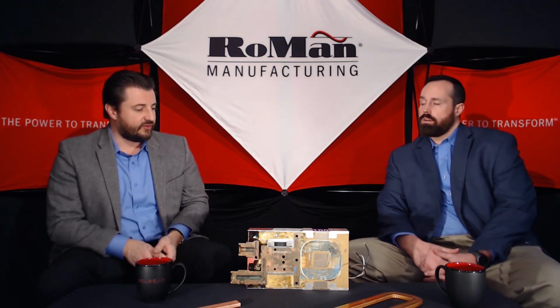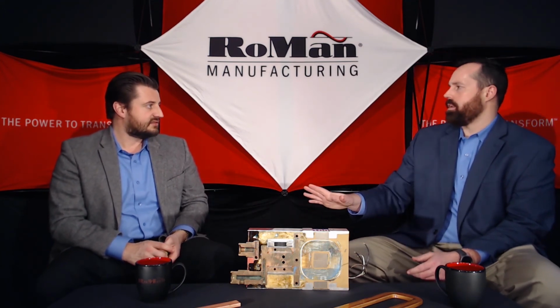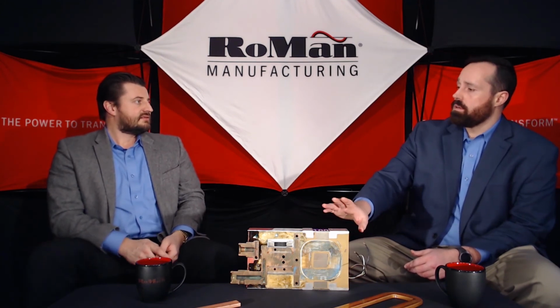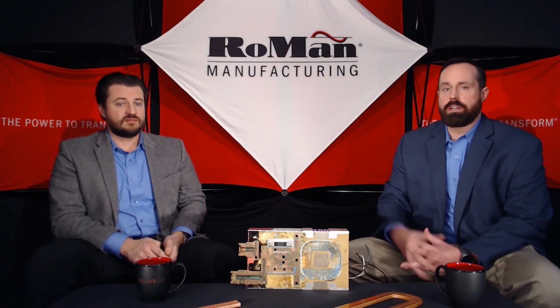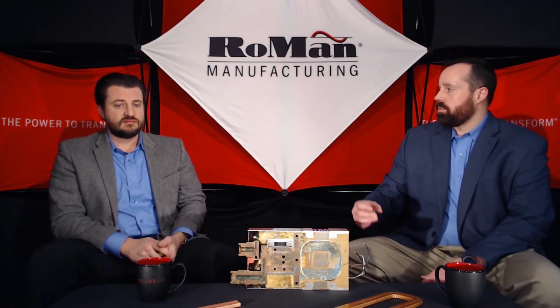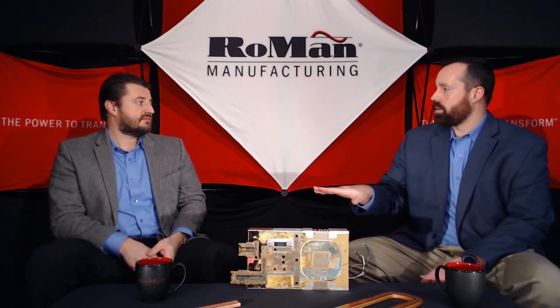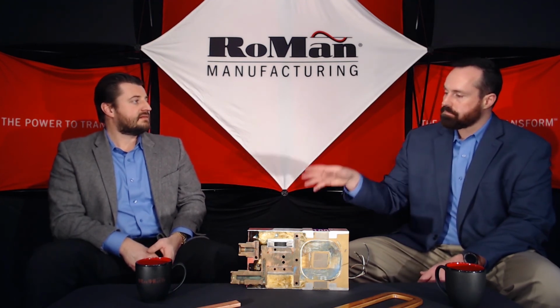Now, with anything, I'm sure there are possibly some downsides. Do you have any thoughts on that? As with any technology, there are always trade-offs. With water flow, customers have to be very focused on how much water flow they're getting through their process. RoMan thinks ahead of this by installing thermocouples and thermal switches within the transformer itself. This will alert the process manager that something is not getting flow and the transformer is overheating. On the other hand, customers themselves will place flow switches and flow meters somewhere along their process, and in that way they can identify if there's any lack of water flow leading to an overheating situation.